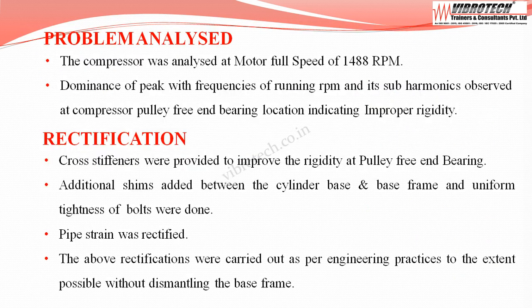The compressor was analyzed at motor full speed of 1488 rpm. Dominance of peaks with frequencies of running rpm and its sub-harmonics was observed at the compressor pulley free end bearing location, indicating improper rigidity.